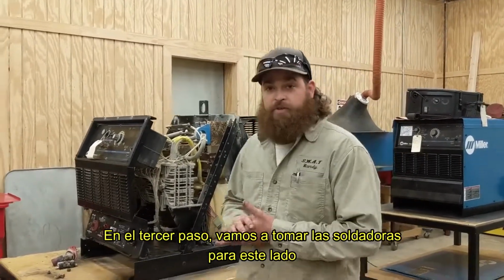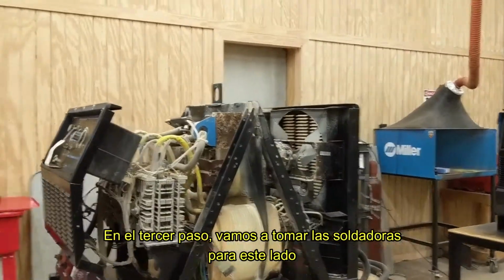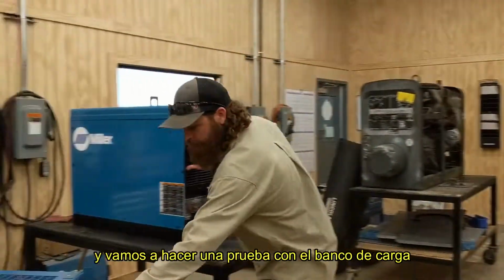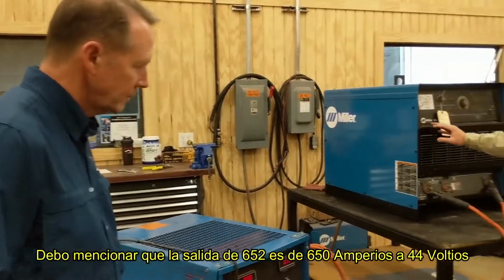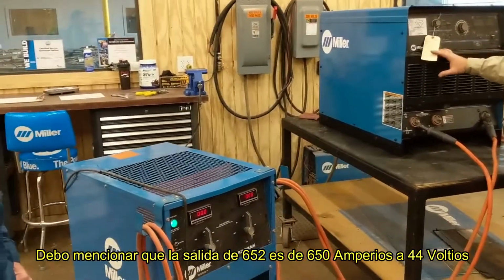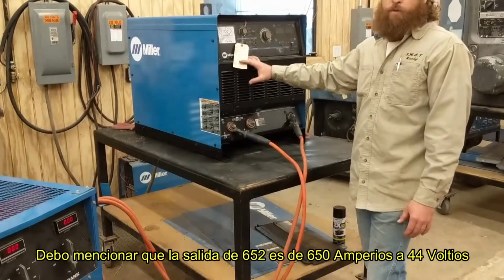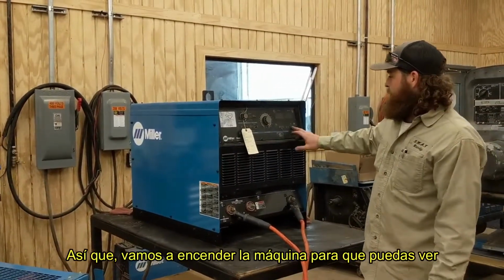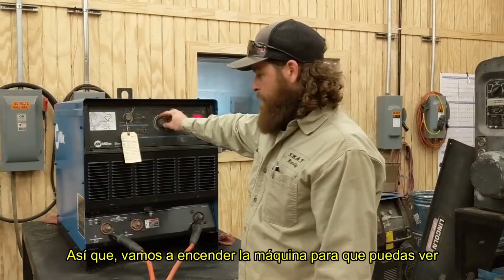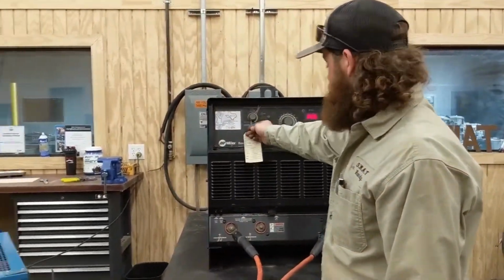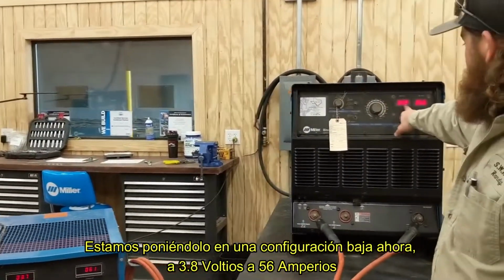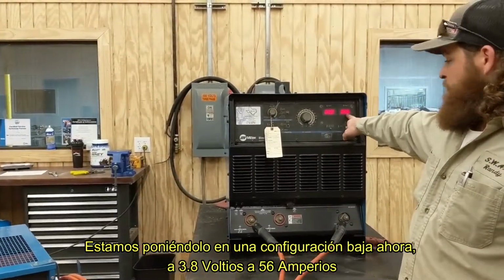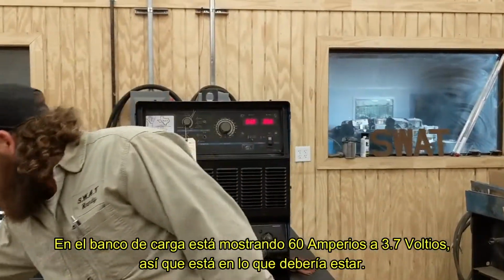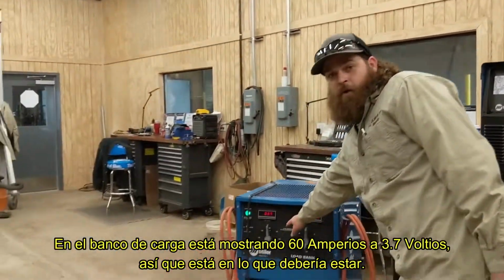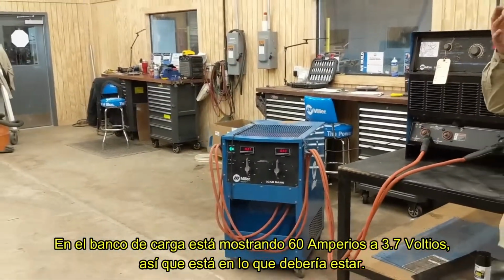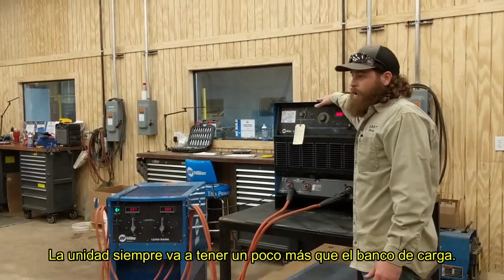So the next step will be step 3. We take these guys, we'll come over, and we will run a load bank test. This machine here is, like I said, a Dimension 652, rated output is 650 amps at 44 volts. So we'll go ahead and power this jewel up. As you can see here, we're set down on lowest setting right now, 3.8 volts at 56 amps. On the load bank, we're showing 60 amps at 3.7 volts, so we're about where we need to be. The unit's always going to be a little hotter than your load bank.